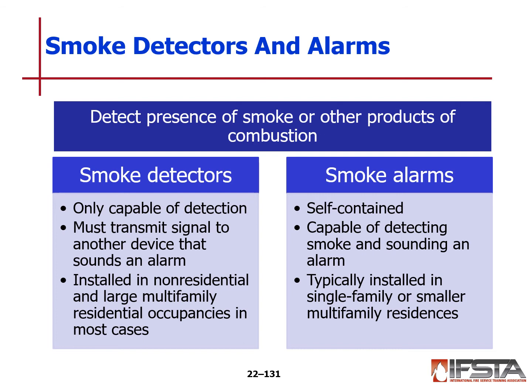With smoke alarms, they're self-contained, capable of detecting smoke and sounding an alarm. Typically they are installed in your single family dwelling or smaller multiple or multi-family residence. So this is what in America is now required in modern or new residential construction, and it's been required for many years now, that you have smoke detectors in specific areas in the home and that they have battery backups and hardwired operation. It is recommended that they are changed out every 10 years.